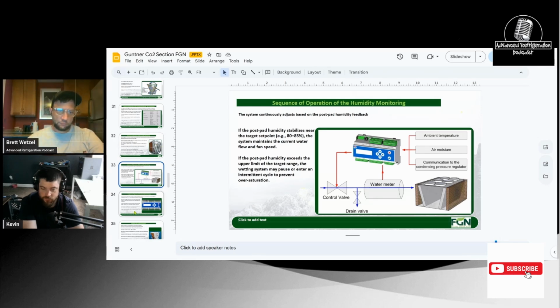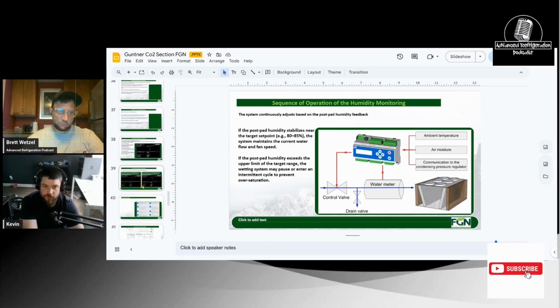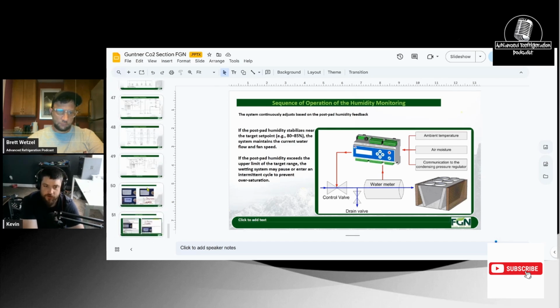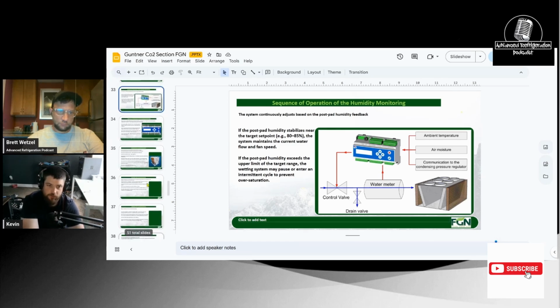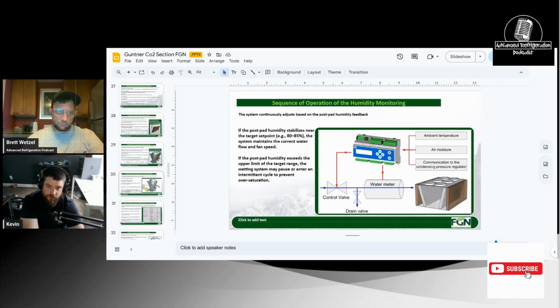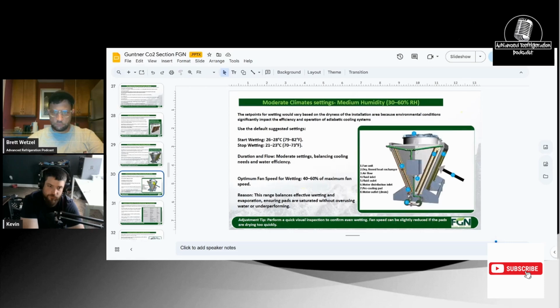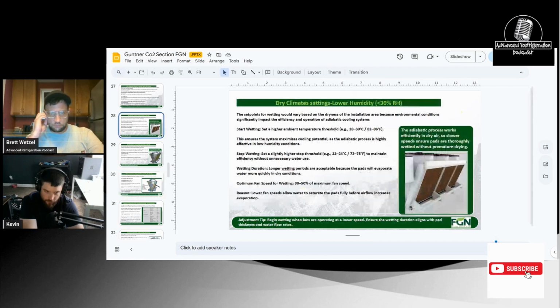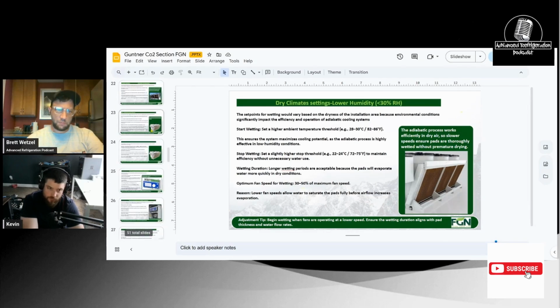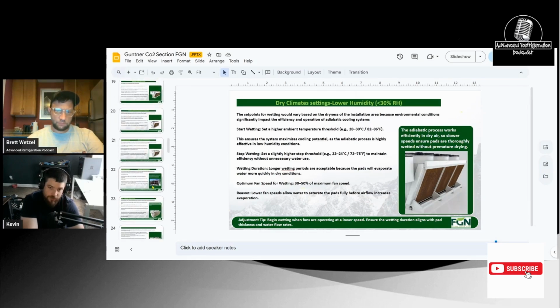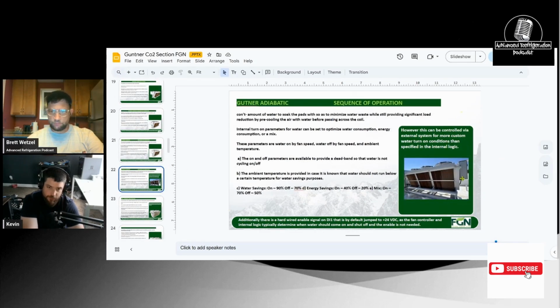If you see a ton of water going down a drain, then you need to call tech support and get a hold of Will and have him troubleshoot this with you. Either the sensors are not reading right, they've had some sensor issues, or you have improperly commissioned or programmed the water setup, and your liters per minute may not be set right on the flow. There's a flow meter on there, or it may not be working properly. So that's one thing to keep in mind with these.